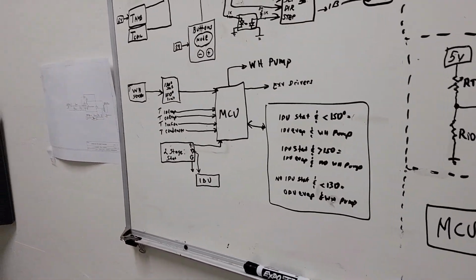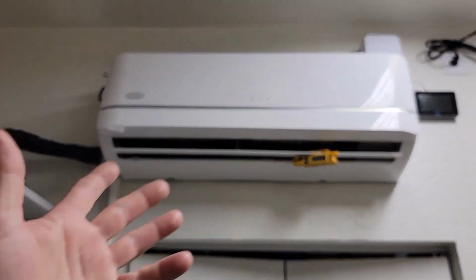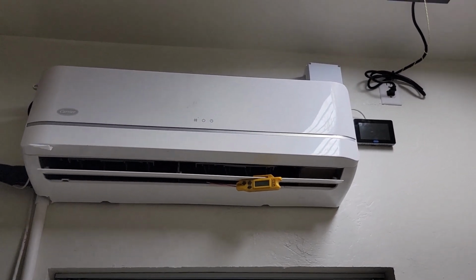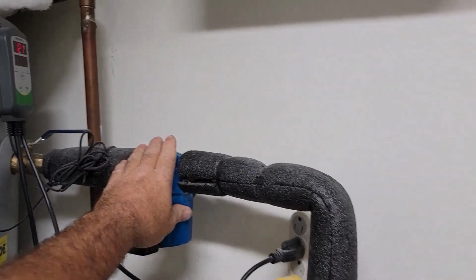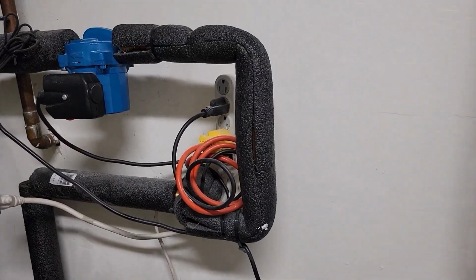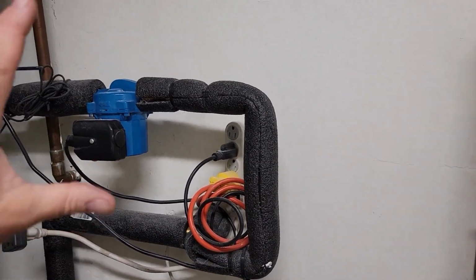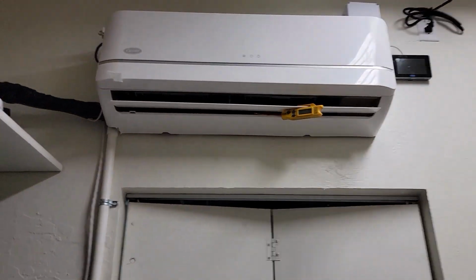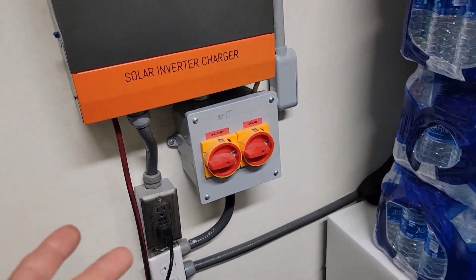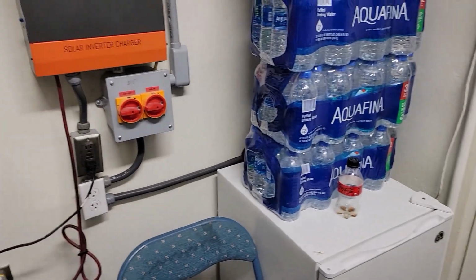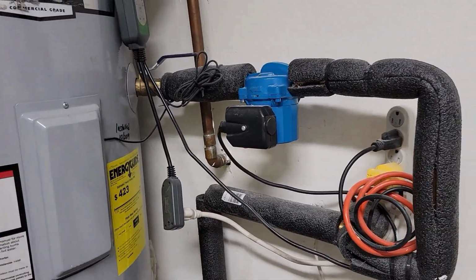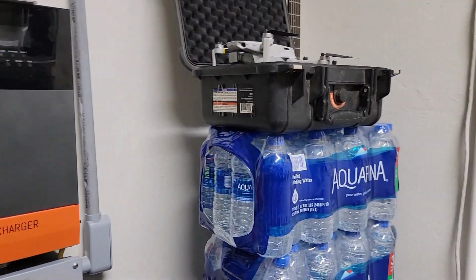Starting to work a little bit on my ideas for further modifying the Frankenstein AC, because right now I have a mini split I hacked and put a fixed speed rotary compressor in out there, and then I have another fixed speed rotary compressor on my other heat pump thing that heats my water. But the end goal is really to have the water heater and the AC in here both connected to the same compressor, the same unit. So in the summertime, anytime it's cooling, it's going to primarily put the heat into the water, or when the water heater is going to kick on.